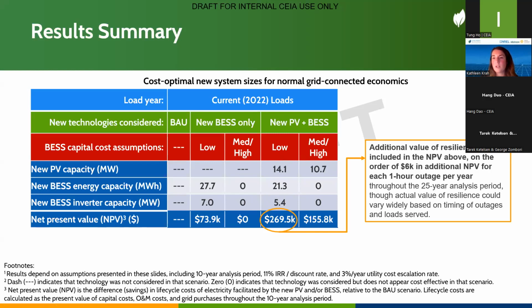And this is not considering the value of resilience of this system. This system could provide an additional $6,000 in net present value for every 1 hour outage that occurs on average per year. So if the site is having on average 5 hours of outage per year, this could be $30,000 in net present value additional to the value shown here.